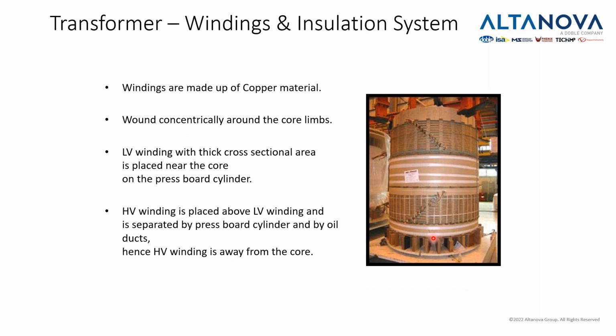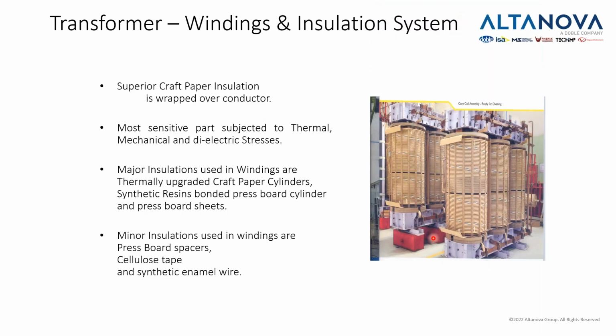Now, the next thing would be windings and insulation system. So after you have created your core, you need to wind something around the core. Windings are made of copper material, wound concentrically around the core limbs, and the low voltage winding is usually near the core, and the high voltage winding is above the low voltage winding. They're all separated by pressboard and paper and oil in order to insulate one from each other.